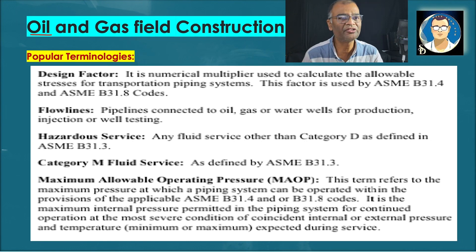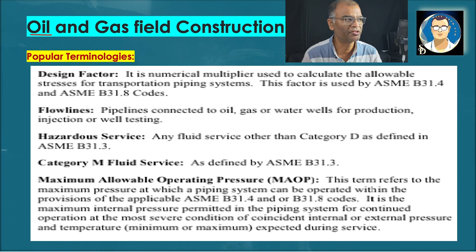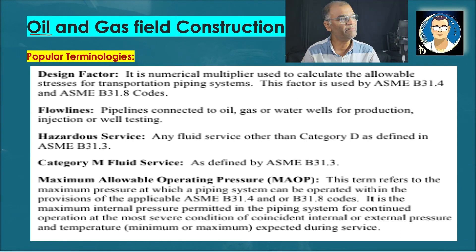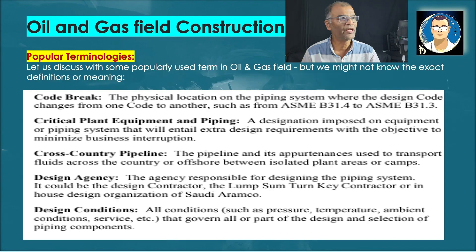Maximum Allowable Operating Pressure, or MAOP, is a term very widely used in hydrotest field. We always check the MAOP of the line in comparison with the hydrotest pressure. In short, MAOP is the maximum operating pressure of the line, based on which the designer does all calculations to determine pipe diameter, pipe thickness, and pipe material.